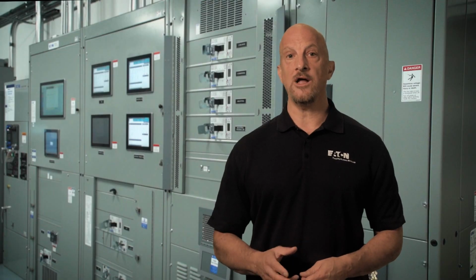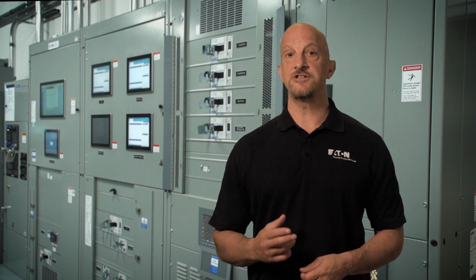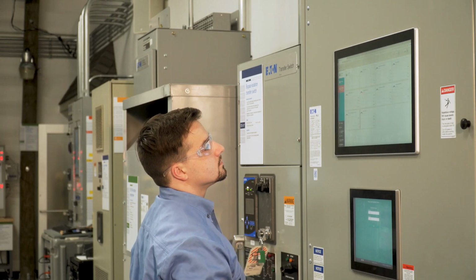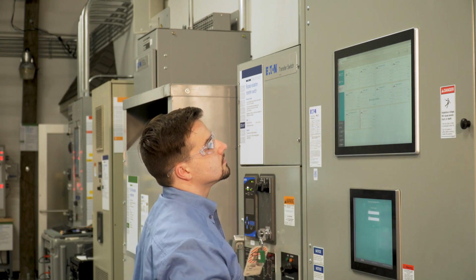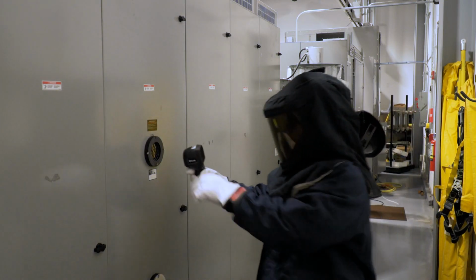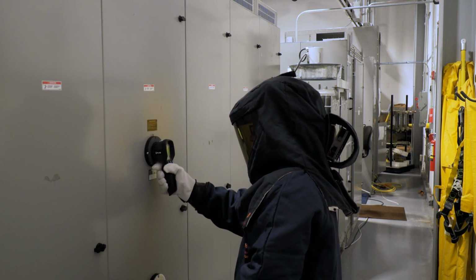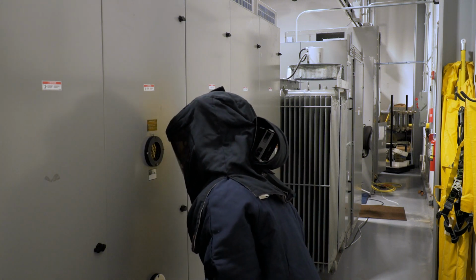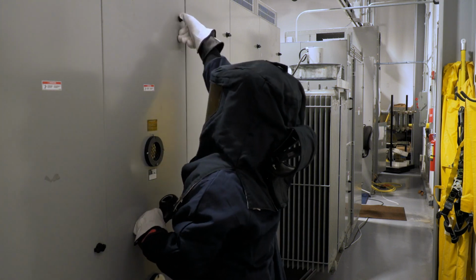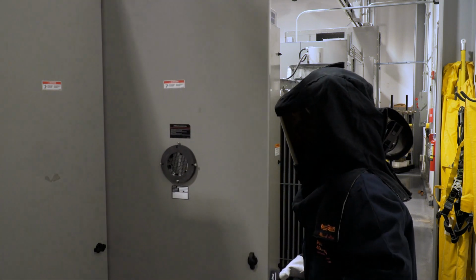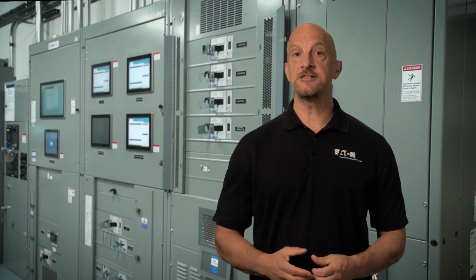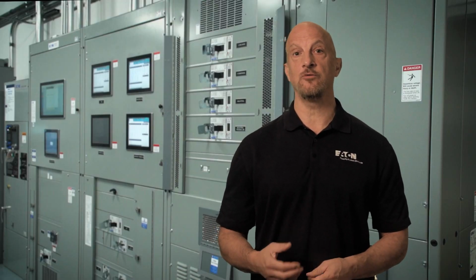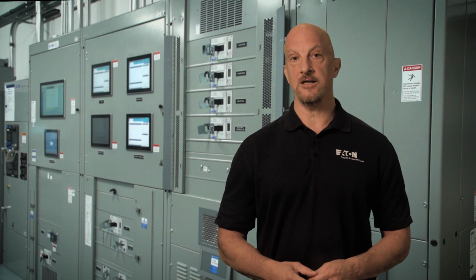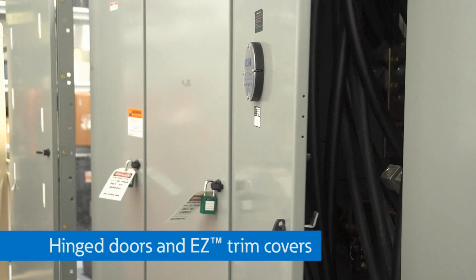These two reasons are why you don't need any special PPE when you simply walk past the gear or stop for a moment or two to examine something visually from outside the gear. To perform IR scans on most of this equipment, covers need to be removed, which could result in arc flash or shock hazards. So what's the solution? For spot checking or troubleshooting specific equipment that may have issues, electrical workers dress in appropriate arc flash suits and carefully remove covers where possible. Eaton has developed many solutions to minimize the risk of removing covers so that they don't fall back into the transformers, switchgear, or panel board.